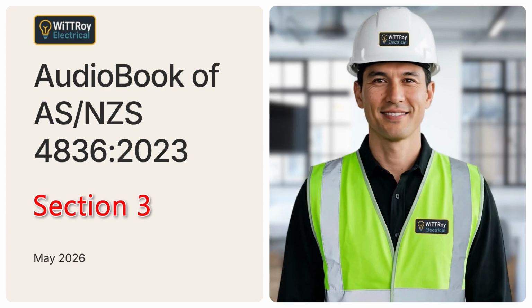Clause 3.1.4.1 General. Clause 3.1.4.1 gives the general rule for securing isolation. The isolating device must be secured in the open position or zero energy state. This is done to prevent accidental or unauthorized operation. Where a locking facility exists, it must be used. The safety idea is simple. If someone is working on the equipment, the isolation must stay in place until it is safe to restore supply.